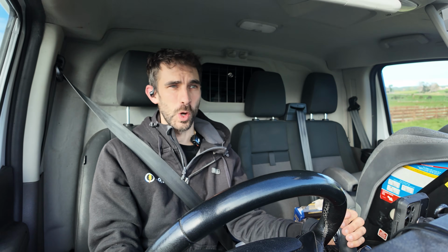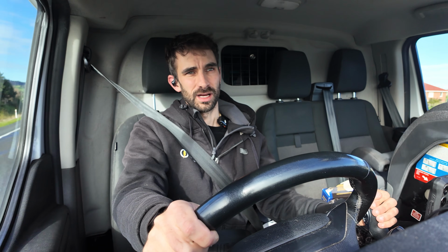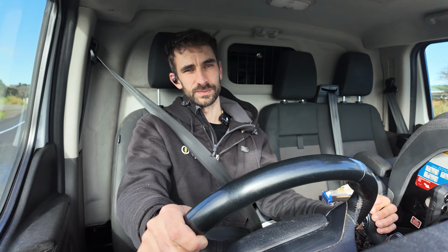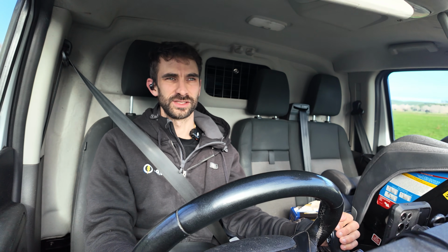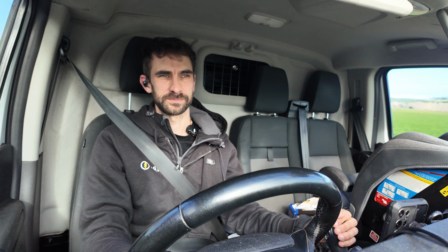A really good earth rod might give you 10 ohms connection. A bad one might give you 100 ohms. Overseas, where they have TT systems, you're actually required to test the integrity of the earthing system. So you put an independent earth electrode nearby, and you need to get a reading of at most 80 or 100 ohms, depending on the jurisdiction.